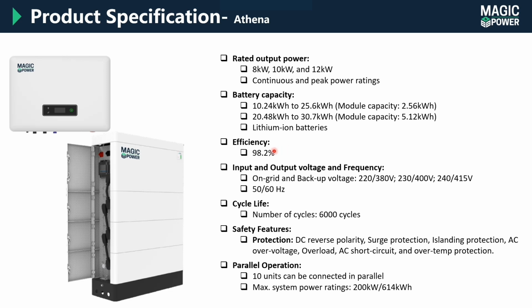The efficiency is 98.2%. Input and output voltages and frequency: the system is three phase, so it could be 380, 400, or 415, depending on the grid standards. The frequency is 50 or 60 hertz. The life cycle for the battery is 6000 cycles, and the safety features again include DC reverse polarity, surge protection, islanding protection, and other protections like over temperature protection or short circuit protection. A maximum of 10 units can be connected in parallel, so the maximum power rating can be 200 kilowatt and 614 kilowatt hours.